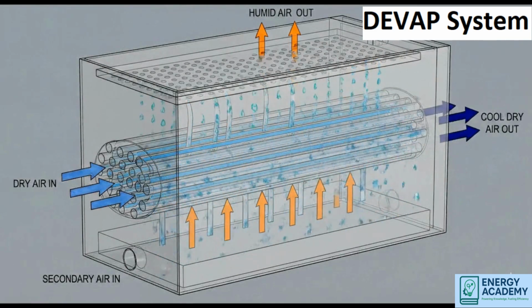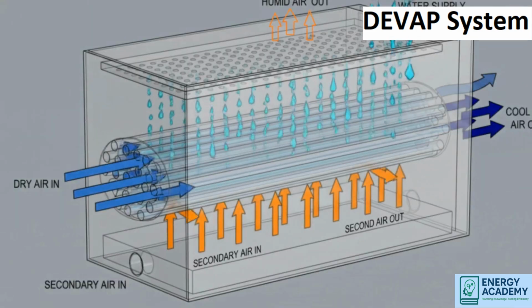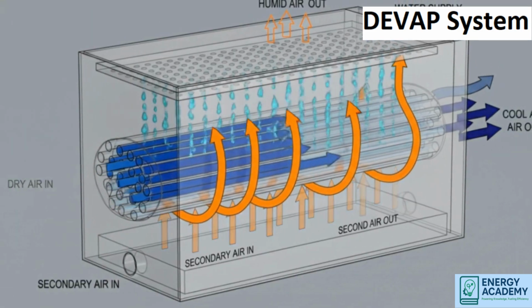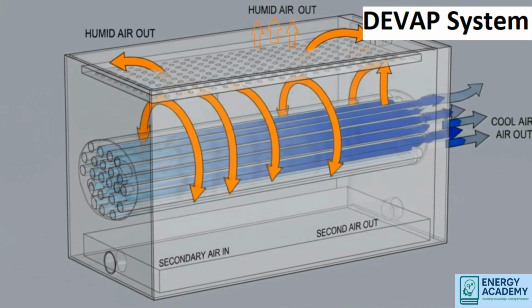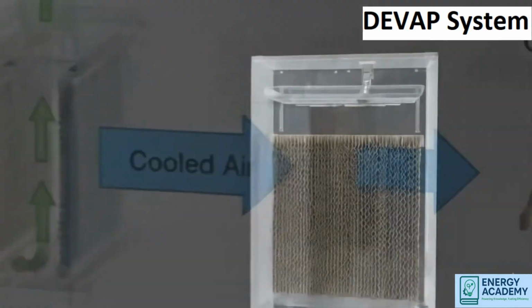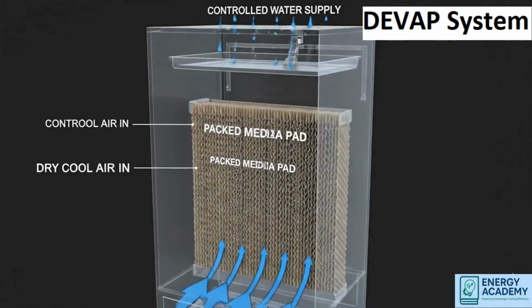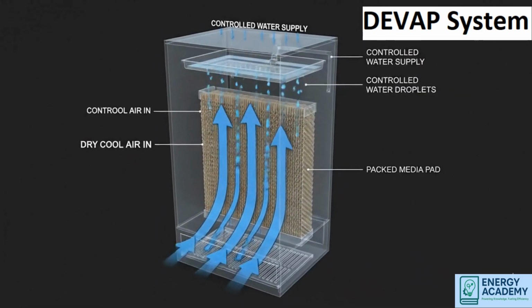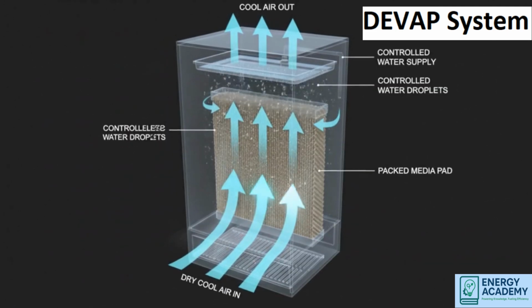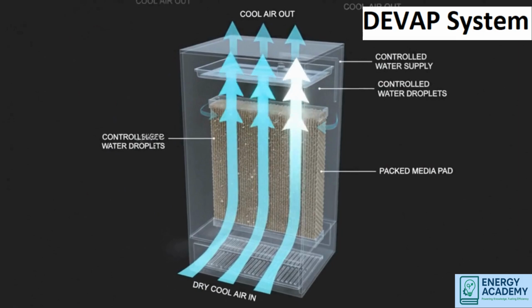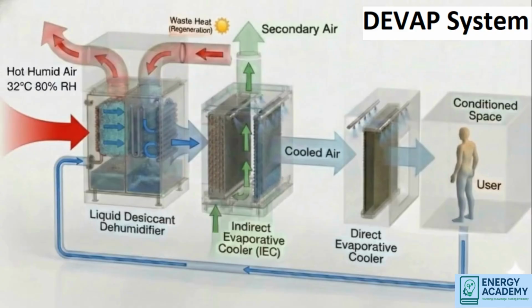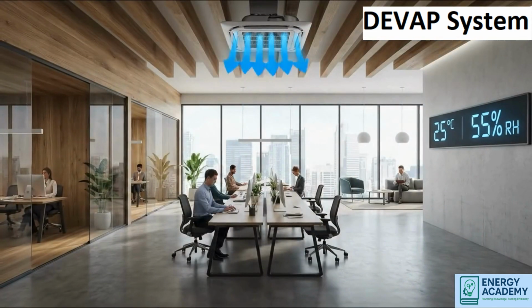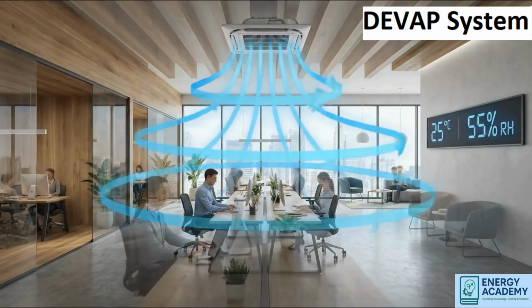And only sensible heat is removed using indirect evaporative cooling, without increasing humidity. After that, this cool, dry air is passed through a direct evaporative cooler and slightly humidified if required. This is to reset the humidity from the dry zone to the comfort zone. And finally, the cool, conditioned air is delivered to the occupied space, achieving comfort with minimal electricity.